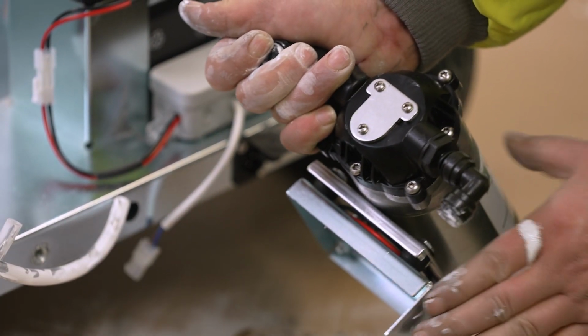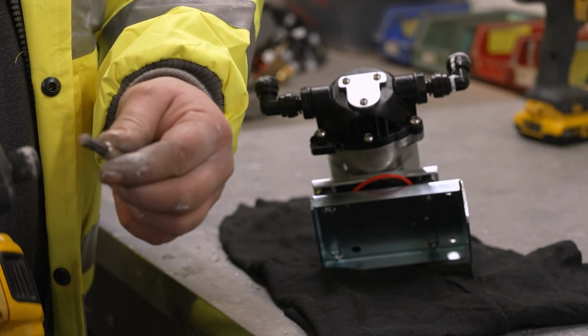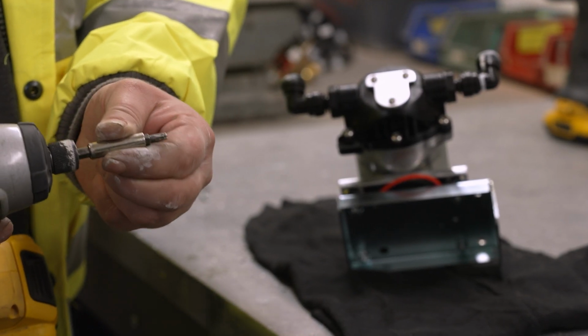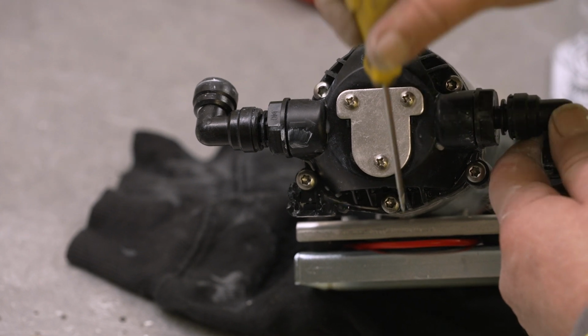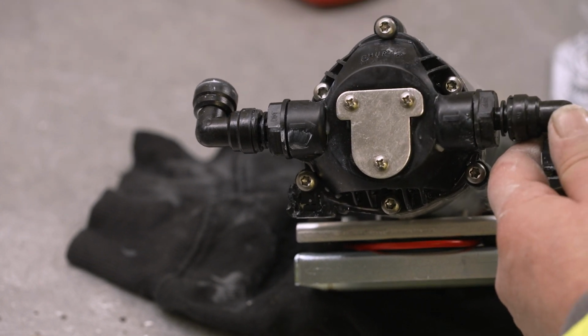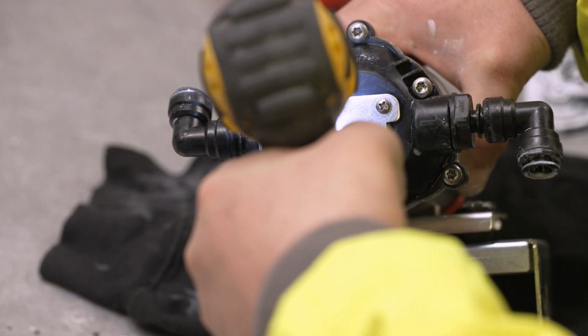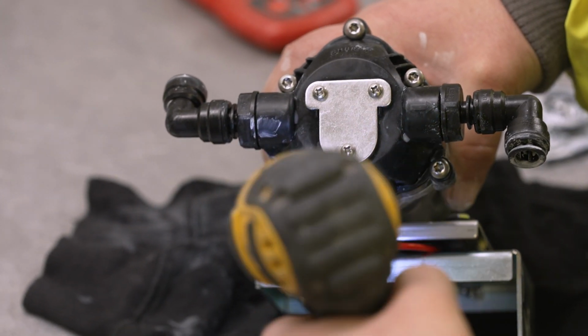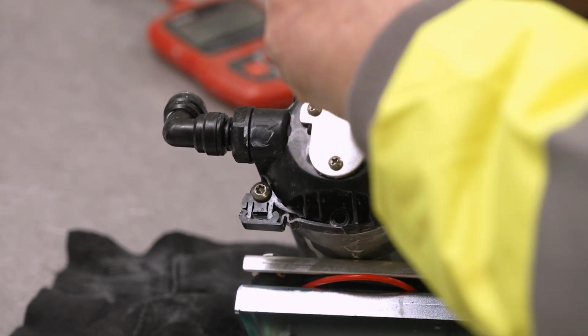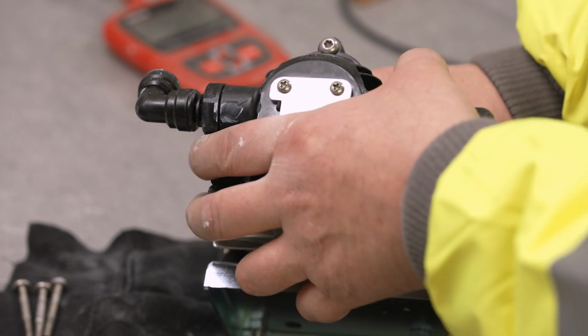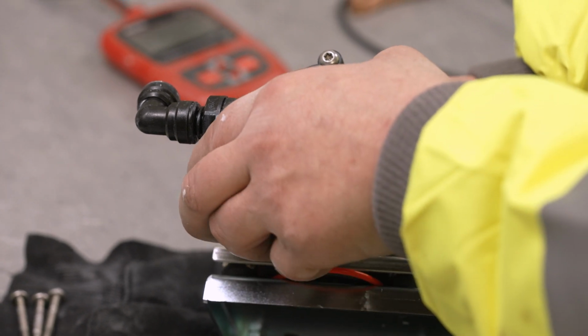Due to the small parts inside the check valve, we recommend moving to an indoor location or workbench for disassembly of the pump. Using a T25 Torx screwdriver bit attached to a cordless drill, remove the 3 inner long screws shown on screen. The pump and the check valve housing will now be separated.